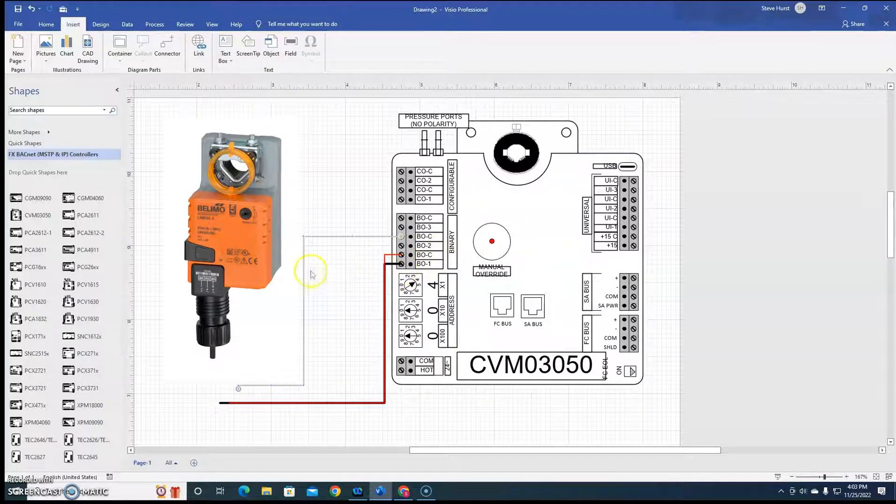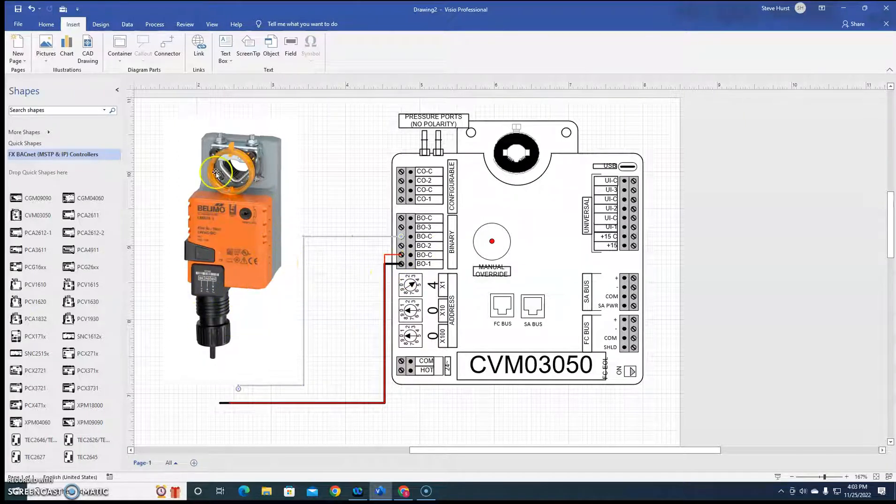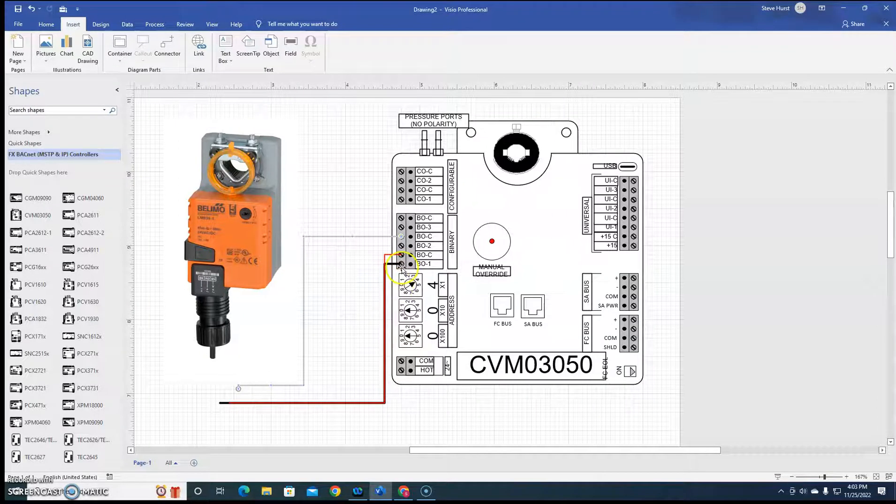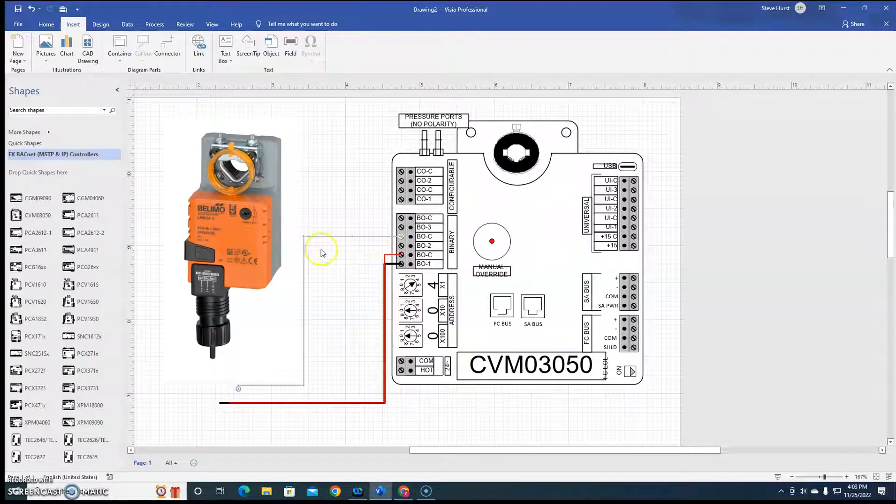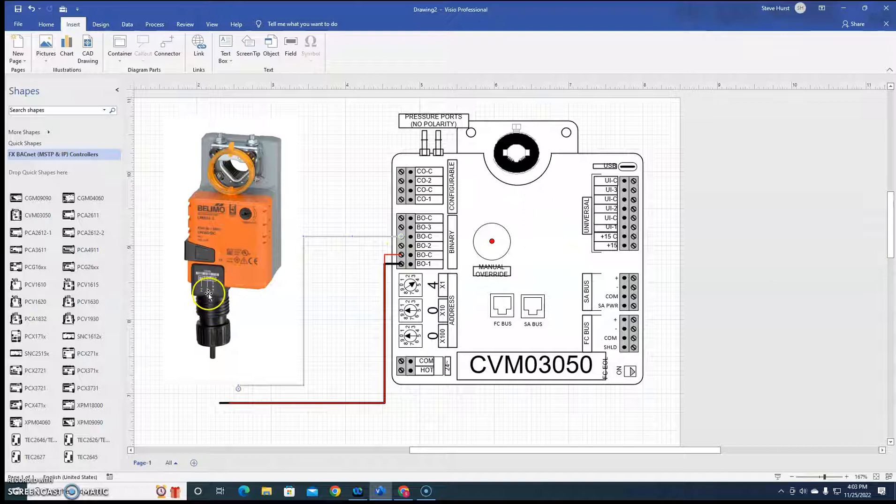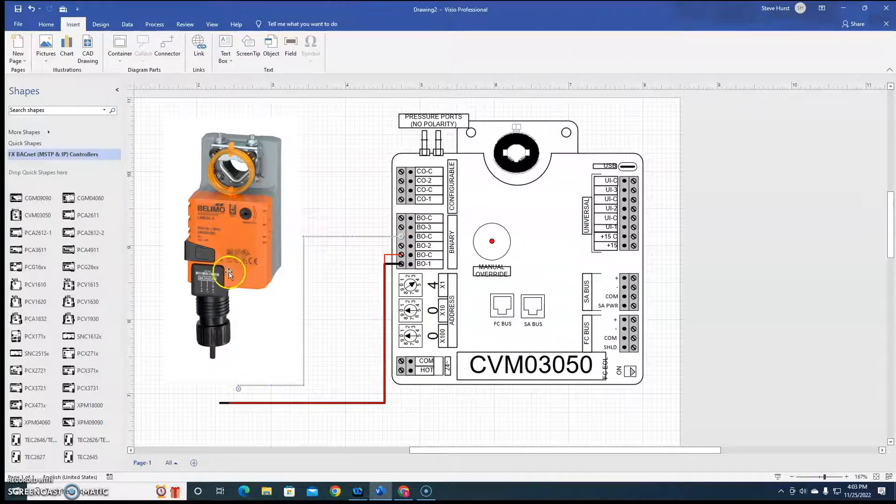So now, the common of the actuator, the shared value of the actuator is actually gonna be hot. And then we're gonna do neutral power to red, to open it, and neutral power to white, to close it.